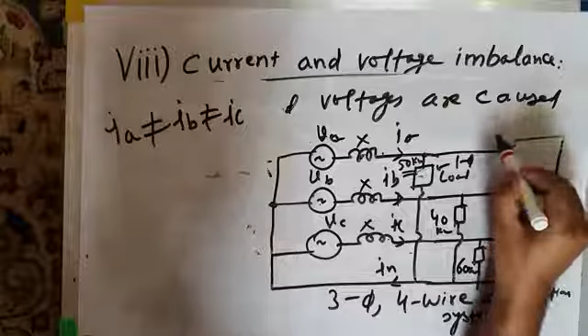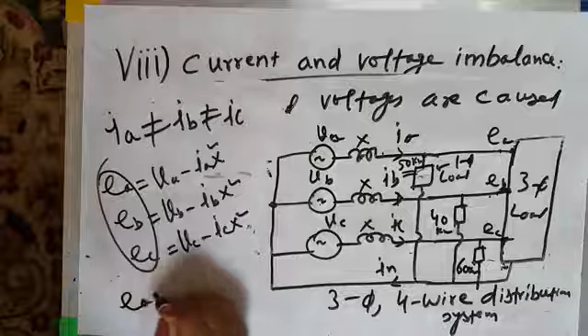So this gives rise to voltage unbalance. If I call this voltage EA, this voltage EB, and this voltage EC, then EA will be equal to VA minus IAX, EB will be equal to VB minus IBX, and EC will be equal to VC minus ICX. Since IA, IB, IC are different, these drops are different, so therefore these voltages are different. So what is the voltage applied across this three-phase load? It is not a balanced voltage, it is an unbalanced voltage. EA is not equal to EB, not equal to EC. So this gives rise to unbalanced three-phase voltages.